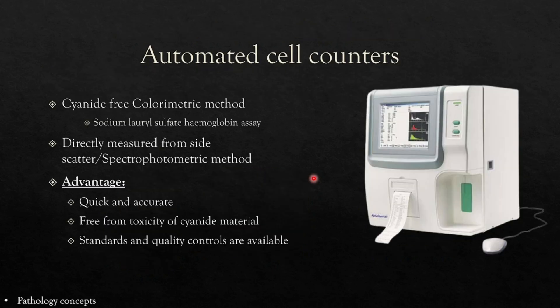Automated cell counters use different techniques to measure hemoglobin, such as the cyanmethemoglobin method, the cyanide-free colorimetric method (sodium lauryl sulfate hemoglobin assay), or direct measurement from side scatter or spectrophotometric methods. Advantages include being quick and accurate, free from toxicity when cyanide-free methods are used, and having available standards and quality controls.